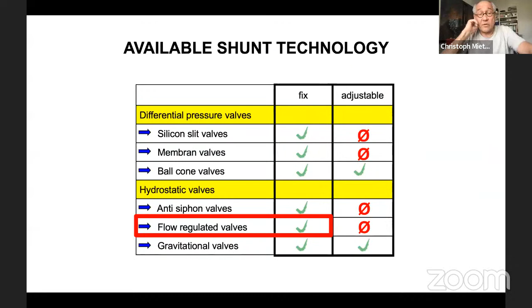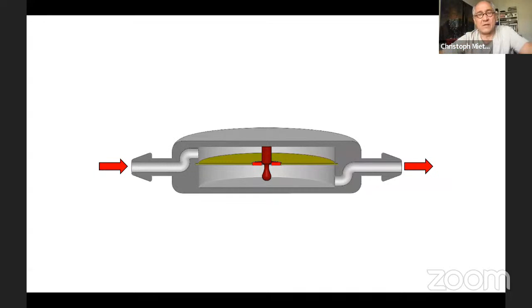The flow-regulated devices — again, I think introduced by Christian Sainte-Rose from Paris in the late 80s. The idea was: if the average production rate is 20 cc per hour, we allow the same amount to be drained regardless of the pressure difference. So if the pressure gets higher, the opening area gets smaller, and therefore the resulting flow through the device remains at the same level.